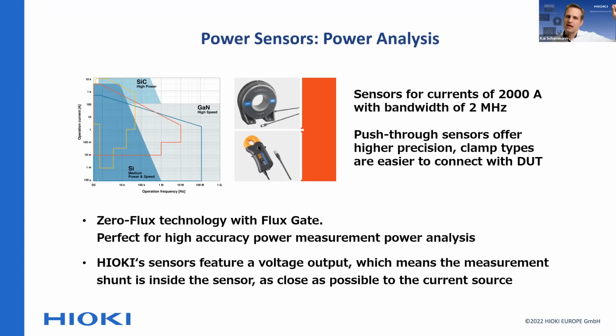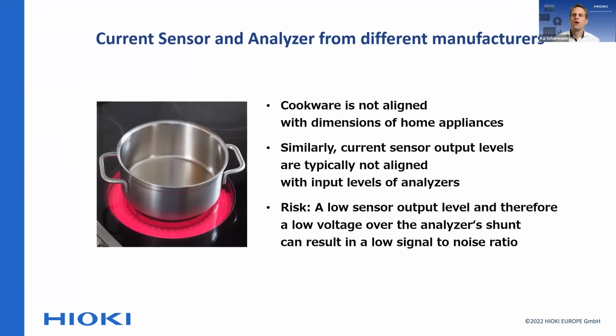But obviously, if it's done inside the current sensor, it's always a very small current that's driven over the shunt. That's the same as if you drove a small current from a current-outputting sensor into the shunt of your measurement device. It's the same thing - in both cases you use shunts. In one case the shunt is in the measurement instrument; in our case, if there is a shunt in the system, it's always in the current sensor. So why do I point out this big difference, and why you have to watch out for the shunt being in the current sensor?